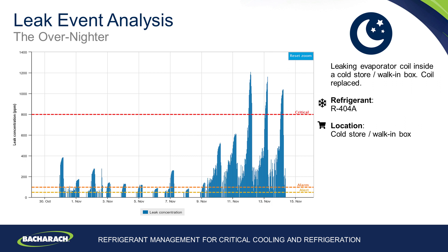In this instance you can see once a coil was replaced the PPM values disappeared. This shows the benefit of the ongoing monitoring system and the leak detection on site, making sure that the fix to the asset was correct and we see no further PPM values indicating any ongoing leak from that system.